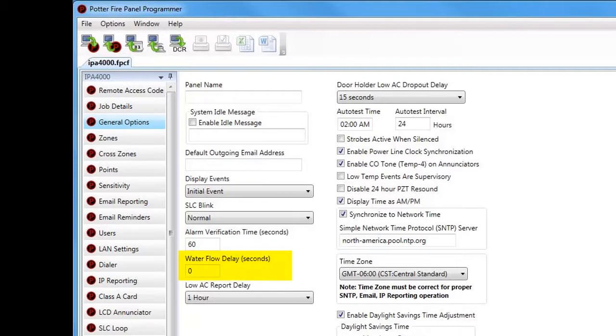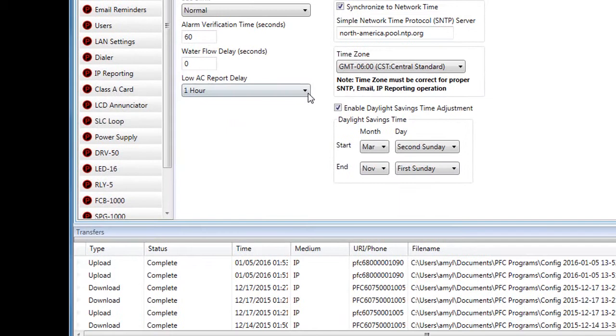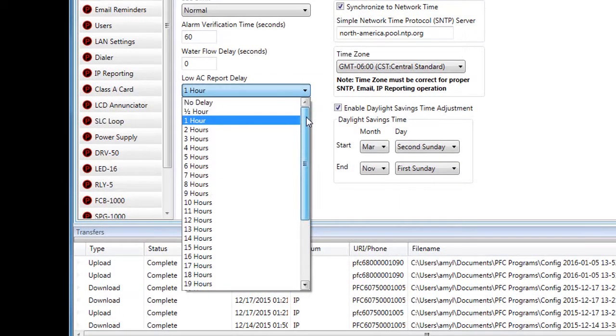Next is Water Flow Delay, in seconds. The default is zero; adding time here will add to the delay already built into the water flow device. Next is AC Report Delay, in hours. This delay refers to how long before an AC loss signal is sent to the central station. The default is one hour, meaning the panel will wait one hour before sending the loss of AC signal to the central station.